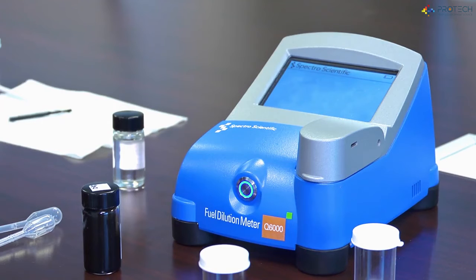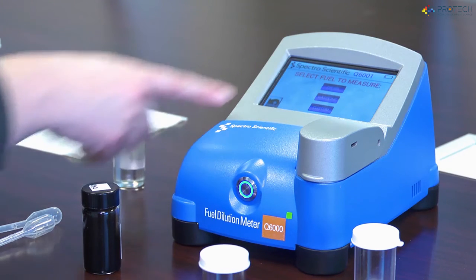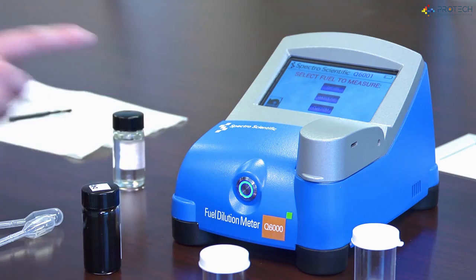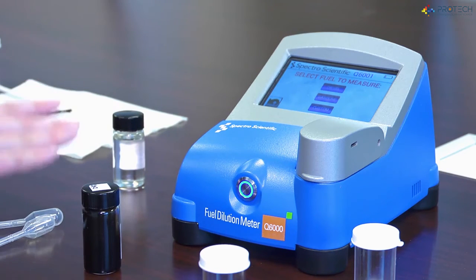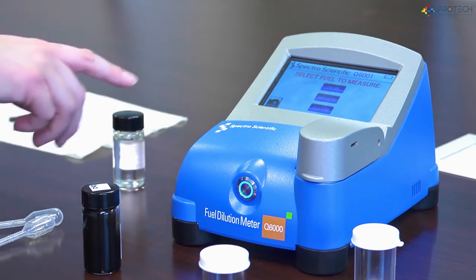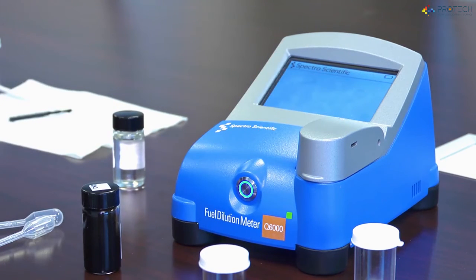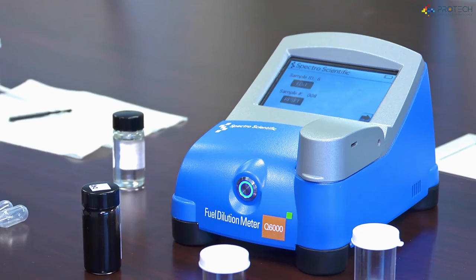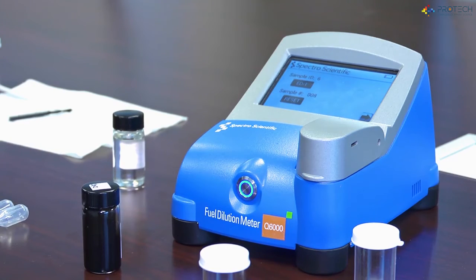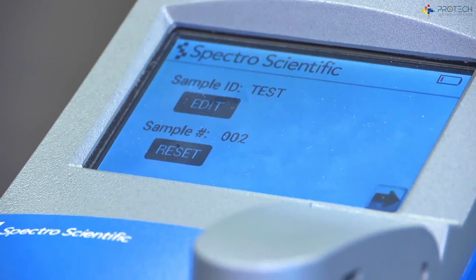Measuring. Select fuel type. Now I'm choosing my calibration slot. Again, this is the model 6001. The 6000 will only have one calibration slot, but here I have my choice of 3. I previously calibrated in diesel. Measuring. So I'm going to push the diesel button. Enter sample identifier, or press arrow to proceed. On this screen, I can enter in a sample ID.